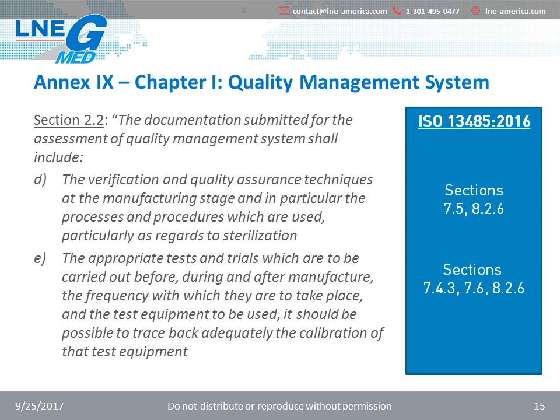You can also find it in section 7.6, related to the control of monitoring and measuring equipment. And I would like to emphasize that this section, 7.6, calls for documented procedures for the validation of the application of computer software used for the monitoring and measurement of requirements. So we are going beyond the equipment itself being validated. In this section, you need to show which tests, but also, with the ISO, the validation of the software used, for example, on the equipment that will do the monitoring. So it is important to identify the equipment and the software, including their version. The version of the software is very important to maintain proper traceability, as it is required above.